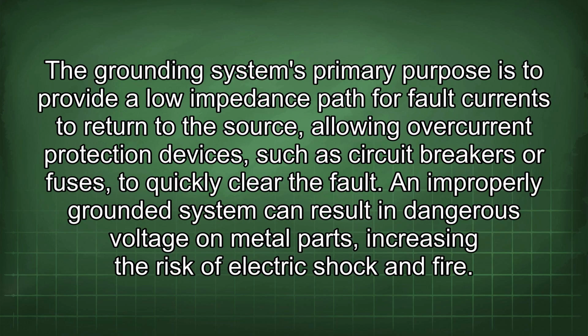The grounding system's primary purpose is to provide a low impedance path for fault currents to return to the source, allowing overcurrent protection devices, such as circuit breakers or fuses, to quickly clear the fault. An improperly grounded system can result in dangerous voltage on metal parts, increasing the risk of electric shock and fire.